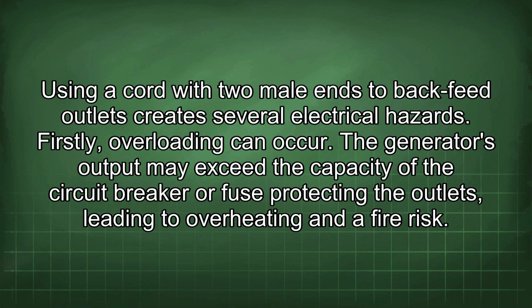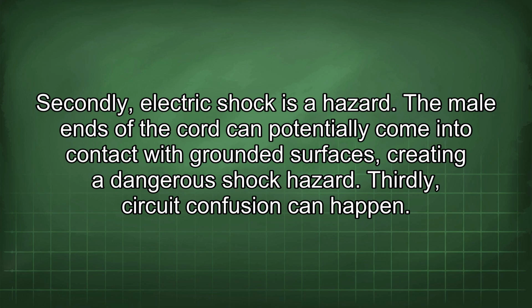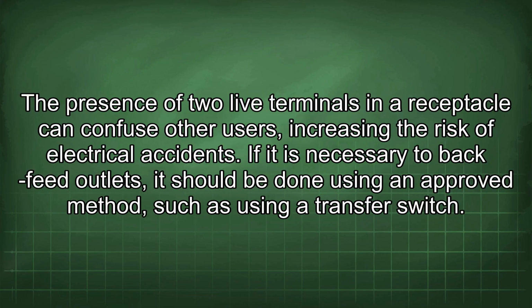Firstly, overloading can occur. The generator's output may exceed the capacity of the circuit breaker or fuse protecting the outlets, leading to overheating and a fire risk. Secondly, electric shock is a hazard. The male ends of the cord can potentially come into contact with grounded surfaces, creating a dangerous shock hazard. Thirdly, circuit confusion can happen. The presence of two live terminals in a receptacle can confuse other users, increasing the risk of electrical accidents.